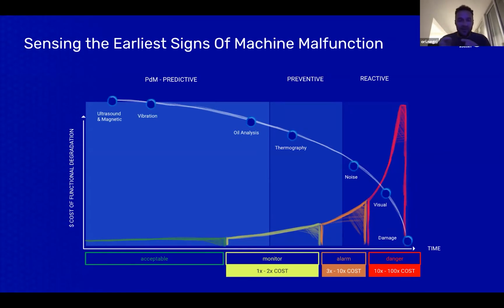Ultrasonic is when there is small friction between, for example, bearing balls, which starts at really high frequency. It can be even 2 years before the actual failure of the bearing, but these frequencies start to show some signs of ultrasonic emission. Also, an electrical example is transient current in induction motors, starting with a really small portion of transient current until it later converts to a short that destroys the motor.